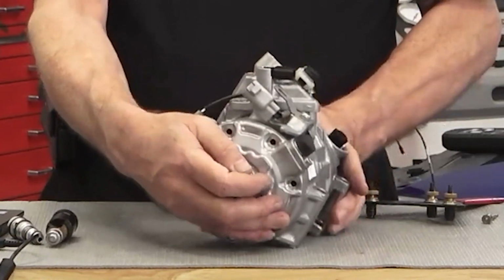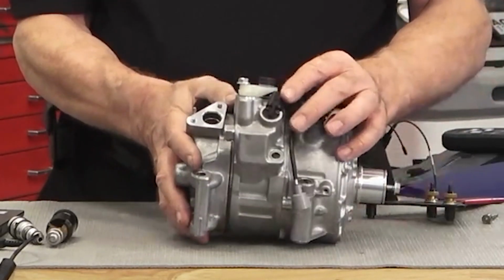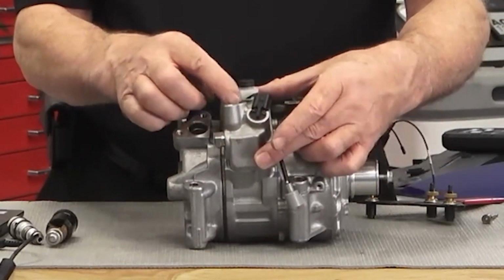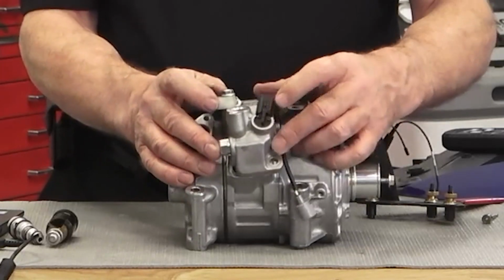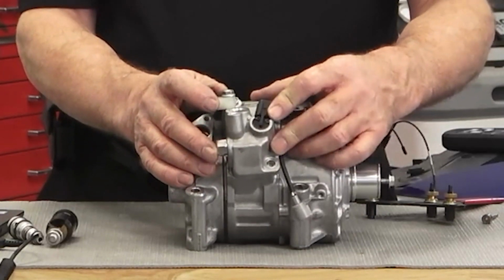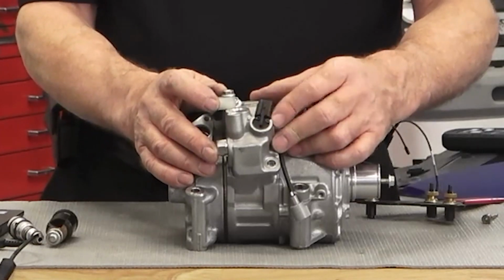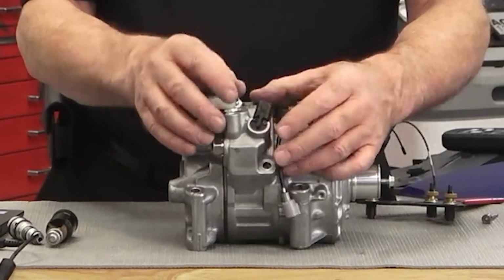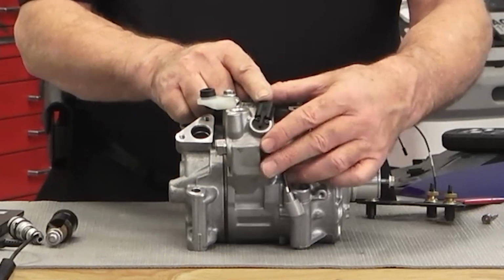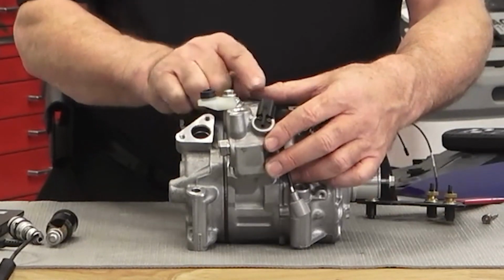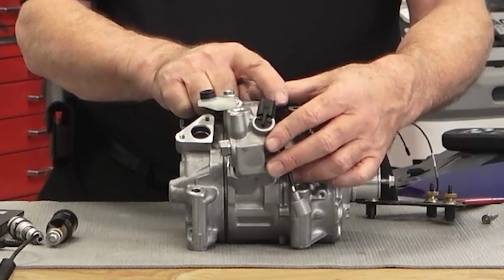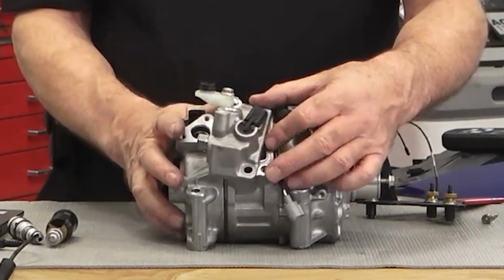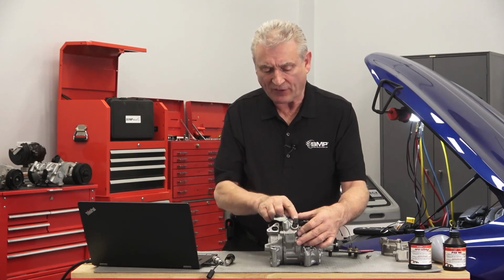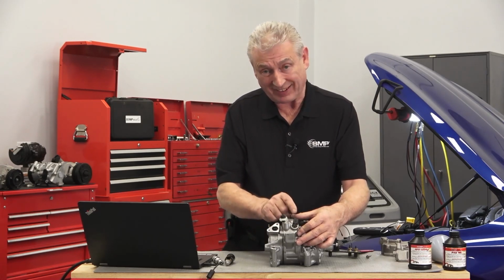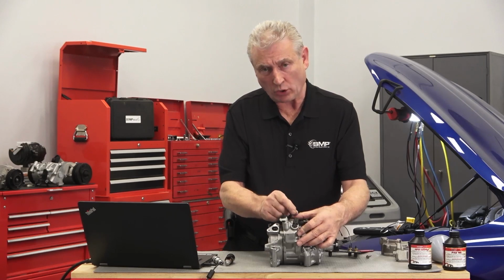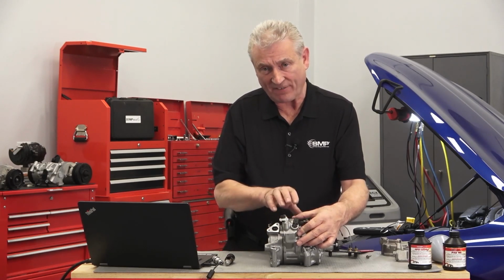The other unique sensor on this compressor is this piece here, mounted on the discharge manifold. It's called a refrigerant volume flow sensor. As its name suggests, it can measure the actual volume of refrigerant passing through the compressor. It's a Hall effect type sensor. It's got a 5-volt reference, a ground, and a signal wire, just like a TPS or an old school MAP sensor. What's different about it is that the signal output changes in proportion to the amount of refrigerant flowing through the compressor.